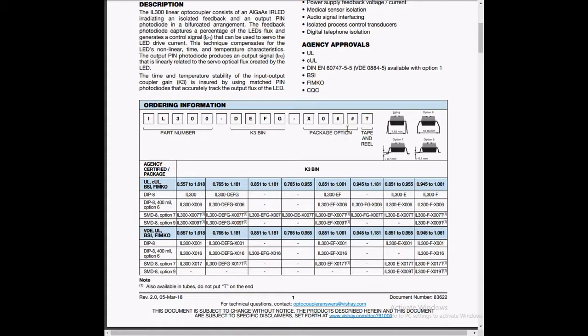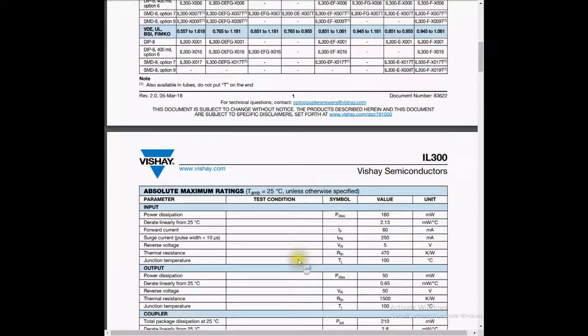And as you can see, they do different widths, and our board was 8mm-ish, so it's probably that body size with the legs coming out to about 8mm. You can go wide. There's a wider body one which is going to give you the best clearance size. And all the clearances and creepages are specified in the medical standards as to what you can and what you can't do.